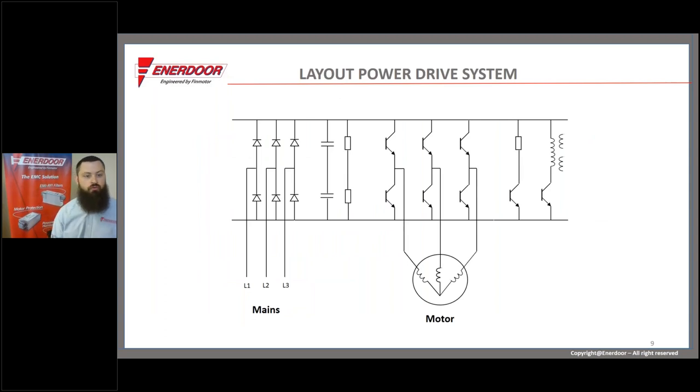There are multiple sources of noise. The key one we deal with in industrial environments is hands-down the VFD — the variable frequency drive. We'll be calling it a drive throughout most of this presentation. There are other noise makers: SCRs, power supplies, CRTs — anything switching DC to AC or AC to DC is going to cause some sort of noise. But the main culprit we see and will be working with today is the variable frequency drive.